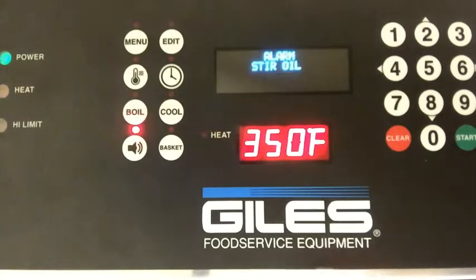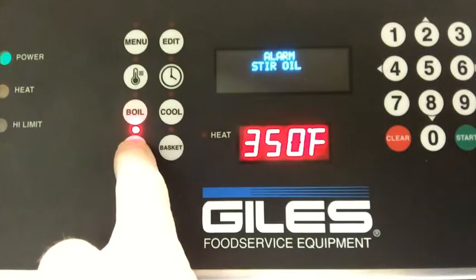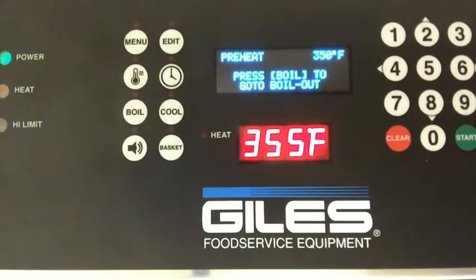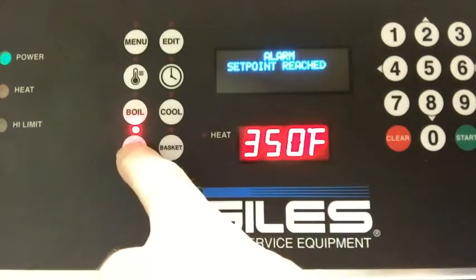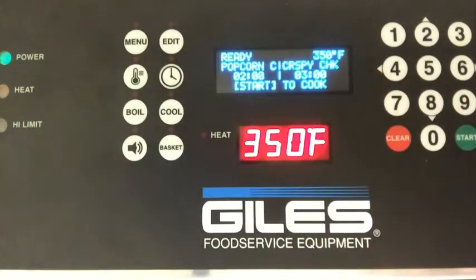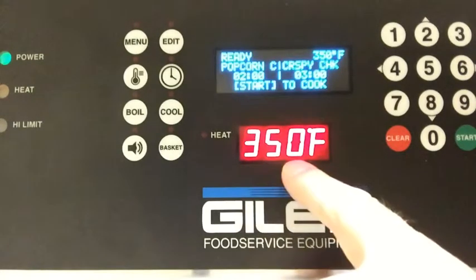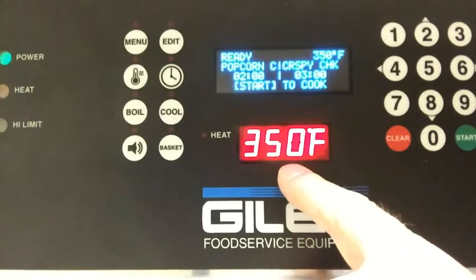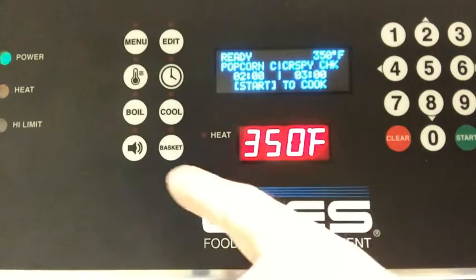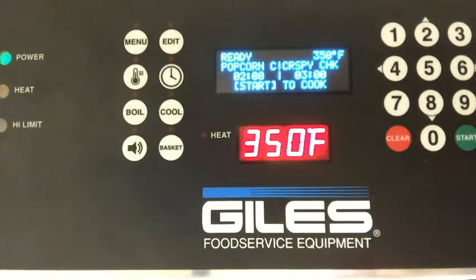Now once it gets there, it's going to go ahead and sound the stir alarm. The stir oil alarm comes on when it reaches temperature to tell you that there's a cold zone underneath and to allow that to mix. You'll stir that oil, bring that cold oil up, and normally it will drop that temperature again. Now it's going to give about 10 seconds to look at it. If it needs continual heating, it will continue to heat. If it's up to temperature, as it is now, it'll now show the set point only, and it'll go ahead and turn the heat light off.